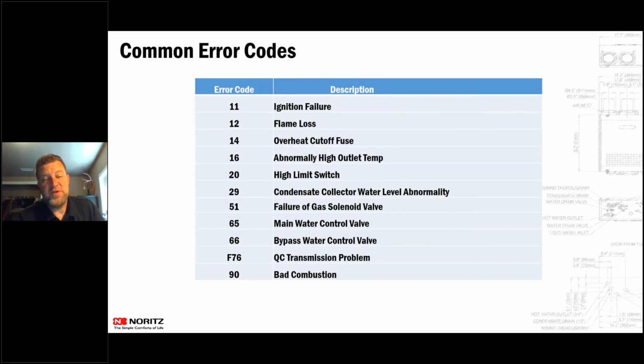So these are the most common error codes that we see out in the field. So 11 is an ignition failure. This could be a multitude of different things. Basically it's saying that it's trying to light and it cannot light. So first thing, always check, make sure that the unit is the correct gas type.